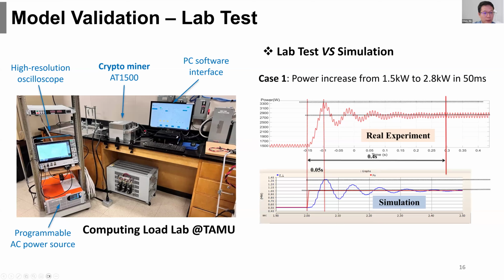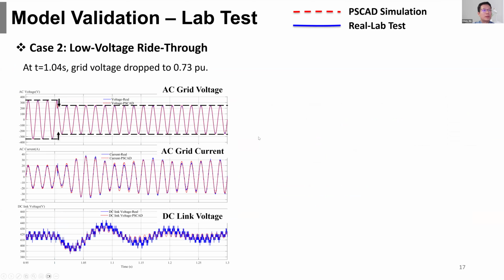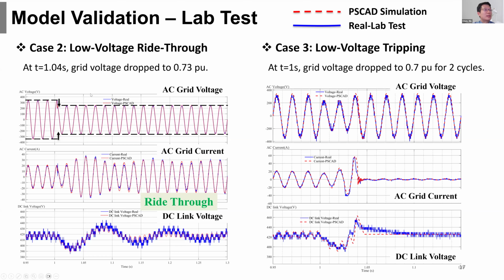In terms of voltage sag, we can simulate both temporary and permanent sags. For example, in this case we simulated the voltage dropping to 0.73 per unit and maintaining at 0.73 — this can last for a long time. Sometimes we can also simulate voltage sag for just a few cycles, but depending on the protection, it can trip or ride through. For both the model and our testing, we've done both.